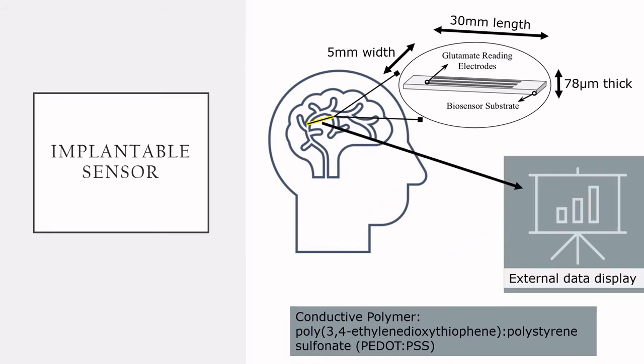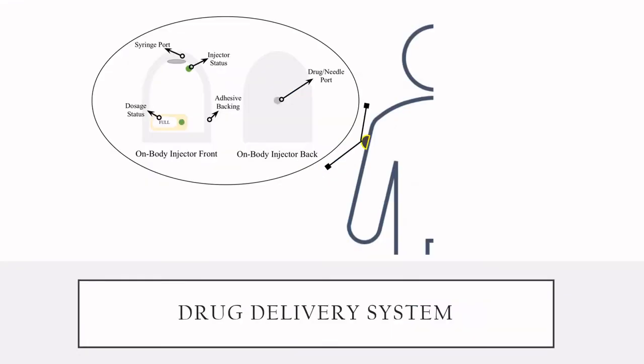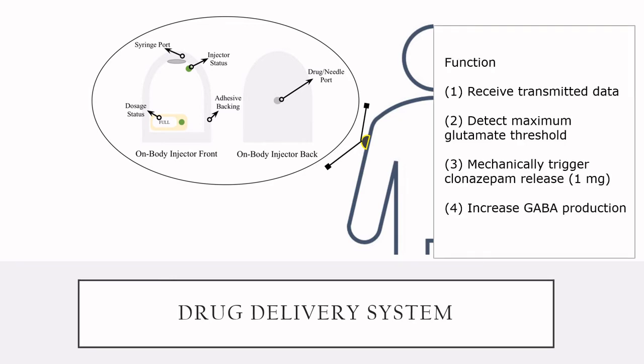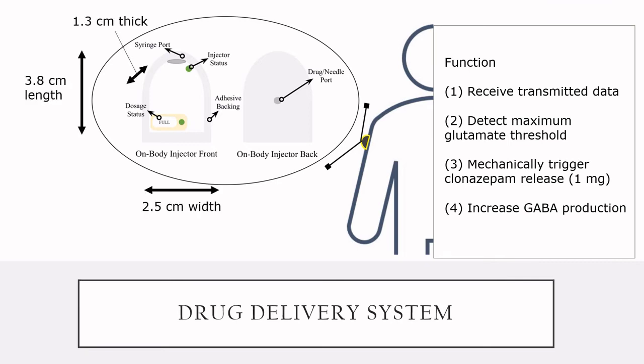The sensor is first implanted for 30 days without the DDS to continuously monitor the patient's glutamate levels and determine the glutamate threshold. The data is transmitted to a receiver for interpretation externally. After 30 days, the DDS is placed on the arm. It receives the information from the sensor and is programmed to detect the glutamate threshold. At threshold, it mechanically triggers the release of 1 milligram dose of clonazepam to increase GABA production and prevent seizure onset. The dimensions are 3.8 by 2.5 centimeters in size with a thickness of 1.3 centimeters.